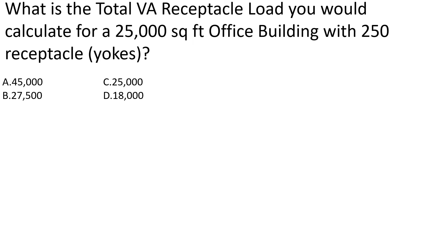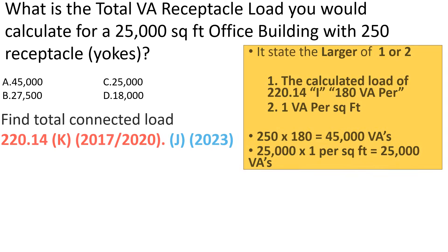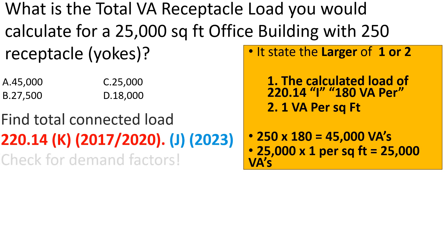What is the total VA receptacle load you would calculate for a 25,000 square foot office building with 250 receptacles? First, find our total connected load. We head to 220.14K if we're in the '17 or '20 code, or 220.14J if we're in the '23 — same information, different name. Both state we must select the larger of two calculations. Part one: calculate at 180 VAs per yoke — 250 receptacles × 180 VAs = 45,000 VAs before demand factors. Part two: calculate at 1 VA per square foot — 25,000 sq ft × 1 = 25,000 VAs. The first part has a demand factor that applies, so we check for demand factors.